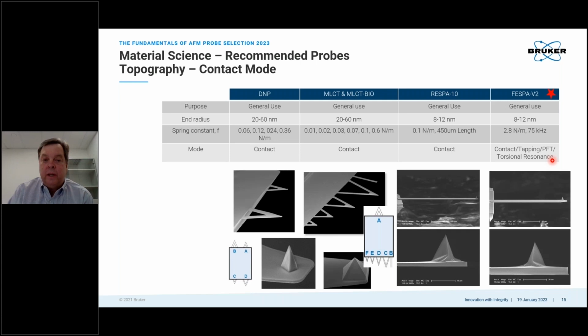For contact mode, if we're talking old school, there's the DNP probe, which is a silicon nitride probe, and the MLCT. These have multiple cantilevers with multiple spring constants, so you would be applying a different amount of force with this. Also, these are nice for force spectroscopy if you want to detect forces at a different level. Then you could choose very soft probes. There's that 0.01, that real long probe I showed you at the beginning. That's this guy here. So these chips will have multiple probes on each one.